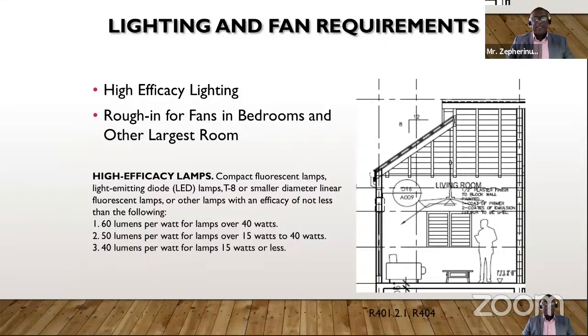The other area that is necessary when it comes to following the requirements of the code is lighting and fan requirements. For the lighting requirements, at least 90% of the installed lighting systems must be high efficacy. In chapter 2 of the code, the definition of high efficacy lamps is as stated here. So as you design your building, you will determine the wattage of the various lamps. And based on the wattage, there is a corresponding lumen for that lamp. So for example, if you're going to be using lamps that are over 40 watts, the lumens should be 60 lumens per watt. If you're using lamps that are over 15 watts, up to 40 watts, you should have 50 lumens per watt. And if it is 15 watts or less, then it is 40 lumens per watt. This is the definition in chapter 2.